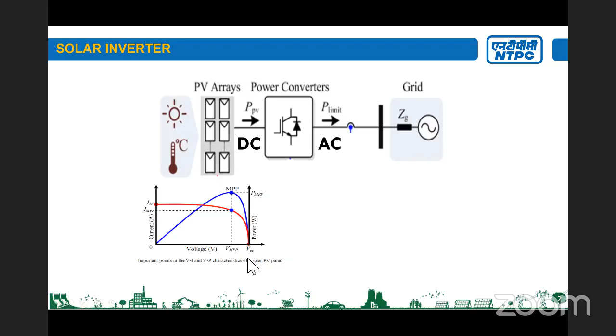I'm covering the topic related to inverter technology. Basically, the solar inverter is the interface between the DC PV array and the AC grid, and it has many responsibilities. One responsibility is to operate the PV at maximum power point, because PV has a parabolic kind of graph that varies with respect to irradiance and temperature. On the grid side, it is also required to operate the solar plant in compliance with grid variation in voltage and frequency, and generate active power based on solar radiation and reactive power based on grid requirement.